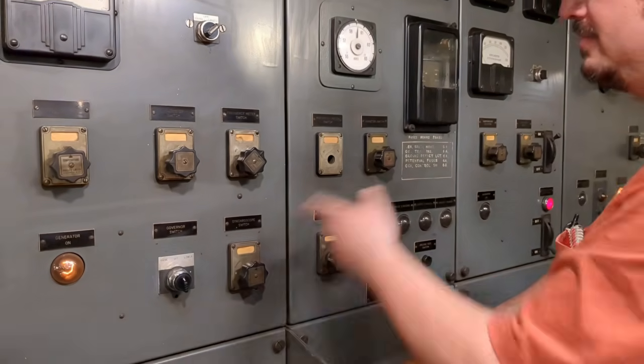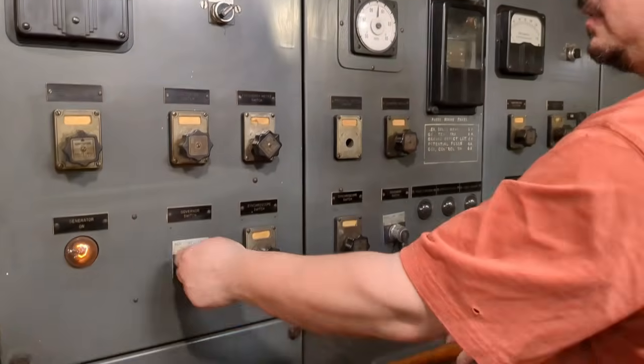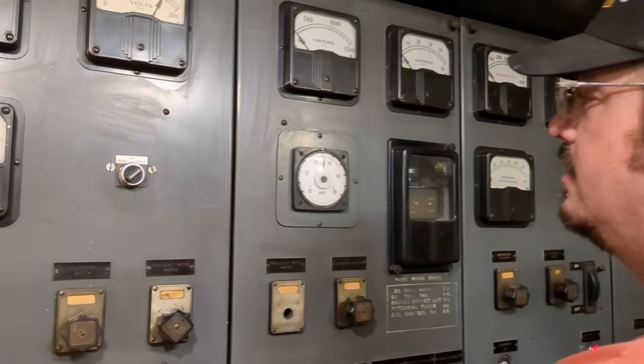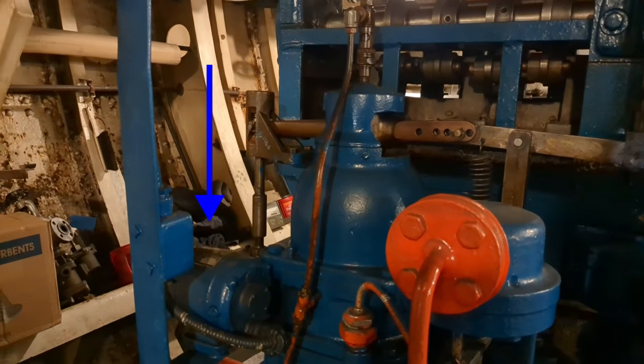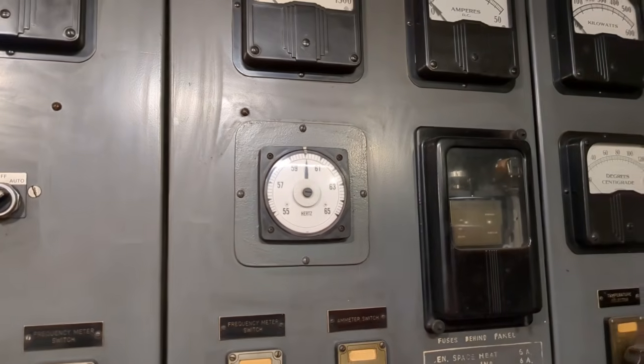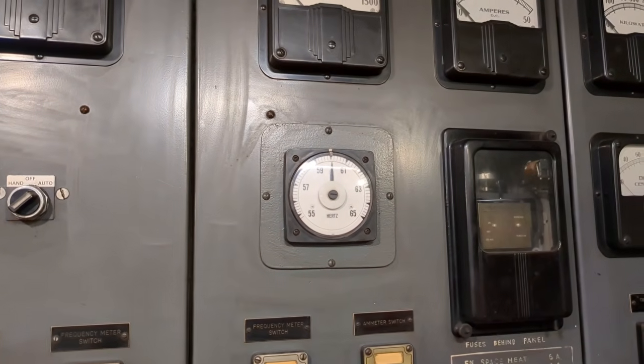When speed fluctuates with changing load, operators must use this switch to correct frequency. The switch operates this small motor attached to the pilot valve linkage. That just controls that little motor on the governor for the turbine.